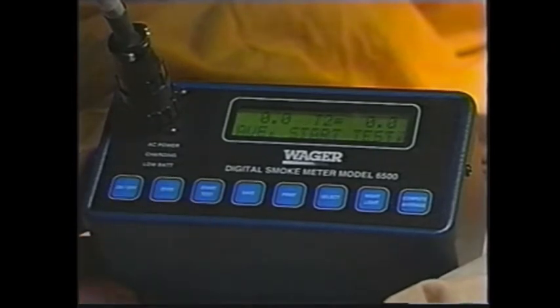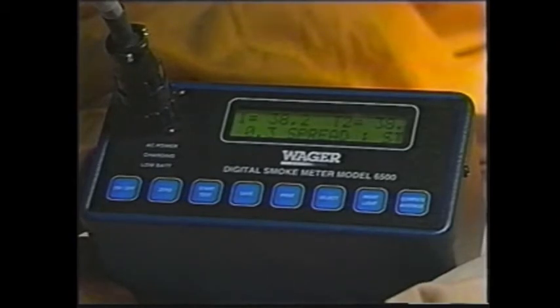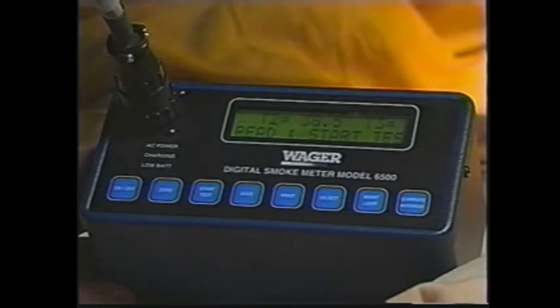Press Start Test. The display shows T2 equals. Repeat the test sequence 2 more times. At the end of the 3 tests, the unit displays the spread. If it is 5% or less, you are ready to do the actual test.